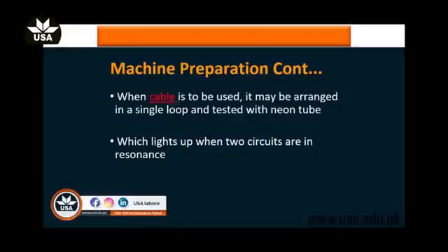When the cable method is to be used, it may be arranged in a single loop and tested with the neon tube, which lights up when the two circuits are in resonance. And this tells about the functioning of the short-wave diathermy.